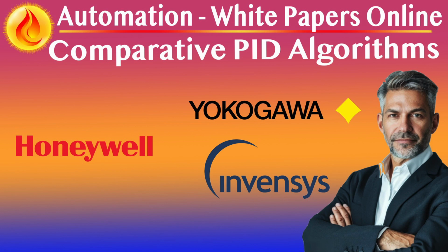Honeywell's system offers two primary PID types. Type A applies proportional action on error, SP minus PV, resulting in aggressive setpoint responses. Type C applies proportional and derivative action on the PV only, smoothing out setpoint transitions. This distinction allows precise structuring of cascade loops, with Type A better for fast inner loops and Type C more suitable for supervisory or outer loops. These modes share identical behavior in load disturbance rejection, but diverge sharply during setpoint changes.